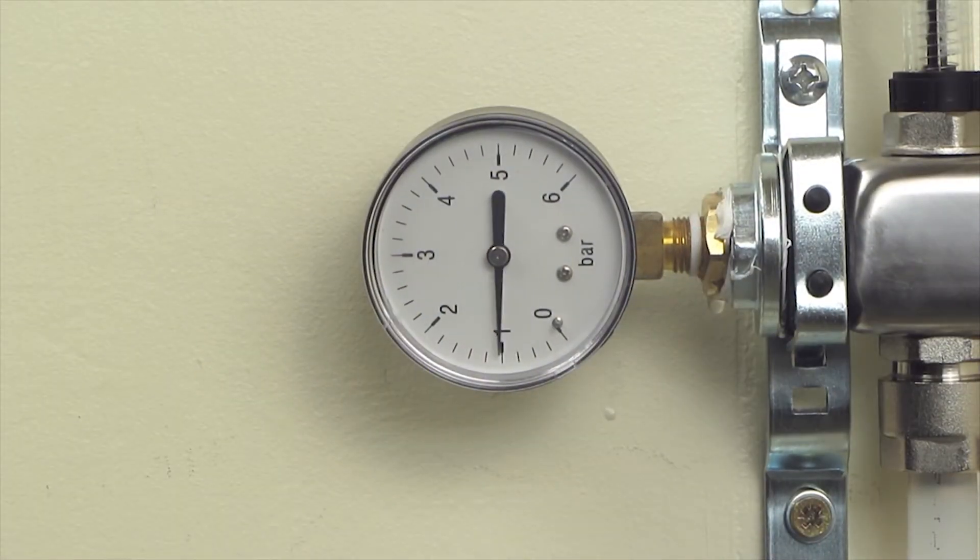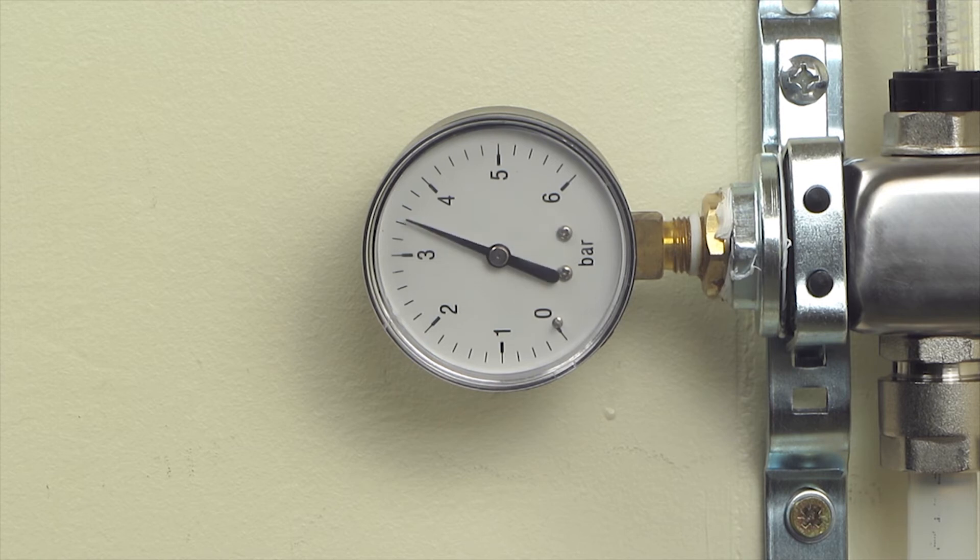Now introduce water into the manifold until 4 bar is reached on the pressure gauge. Leave the manifold under pressure for at least 10 minutes and check for leaks. If any occur, check connections for tightness.